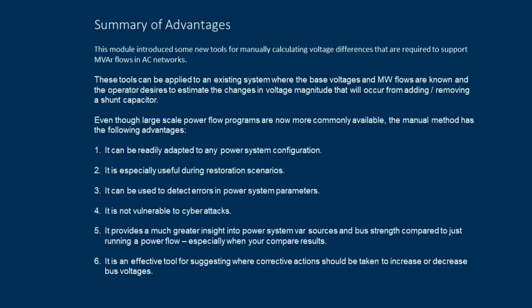And it does provide a much greater degree of insight into power system VAR resources and bus strengths compared to just running the power flow, and especially when you use the two together. When you do the calculations using the TLAR equations and the electrical distance diagrams, and you go check with the power flow how the two agree, you build a really good understanding of what's happening on your system. And finally, it's a good tool for suggesting where corrective actions could be taken to increase or decrease bus voltages.